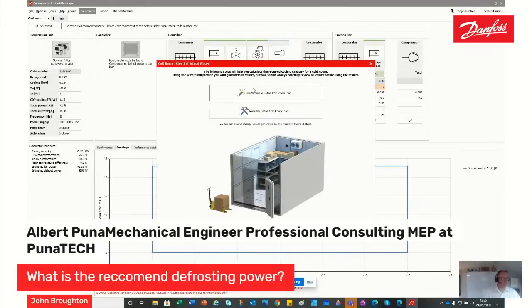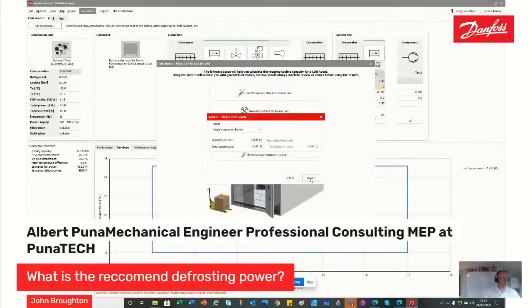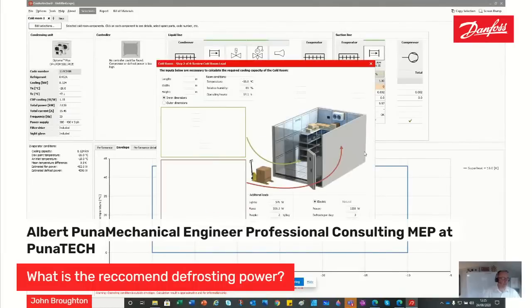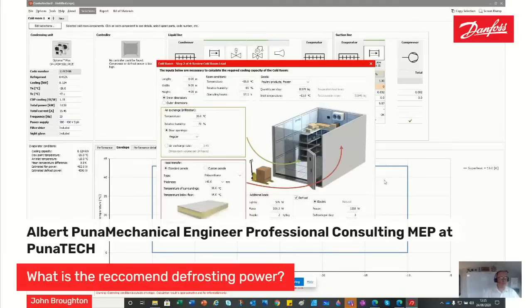So we're just going to run the wizard again. Now as we go through and we get this overview screen, the functionality of the software will give you that recommended defrost power for that evaporator. Now, this is based on application know-how. And as we can see there, the power is just over 5,000 watts or 5 kilowatts.